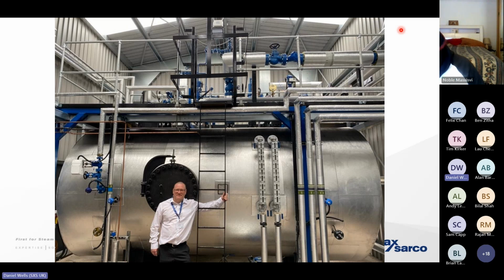So that's my cheery, smiley little red face stood next to one of our steam batteries that we've got in operation down south. Many of you will think, well, that's a steam boiler. Well, that's the intention. It's manufactured to the same code, to the same dimensions. It's got the same safety features as a boiler. The only two things missing are, well, it doesn't have a natural gas burner and it doesn't have a flue.